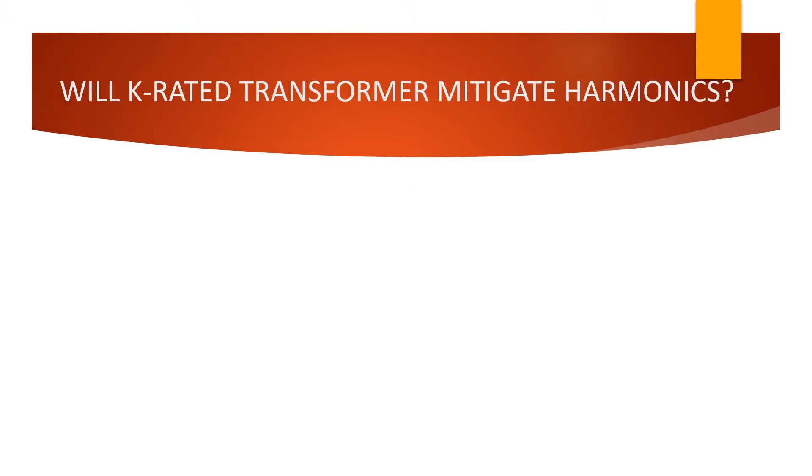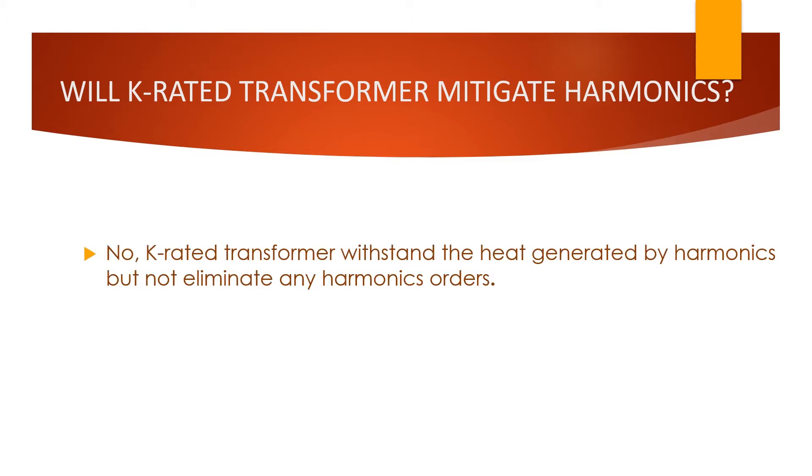Will K-rated transformer mitigate harmonics? Obviously, the answer is no. K-rated transformer is not mitigating the harmonics, but it can withstand the heat generated by harmonics.